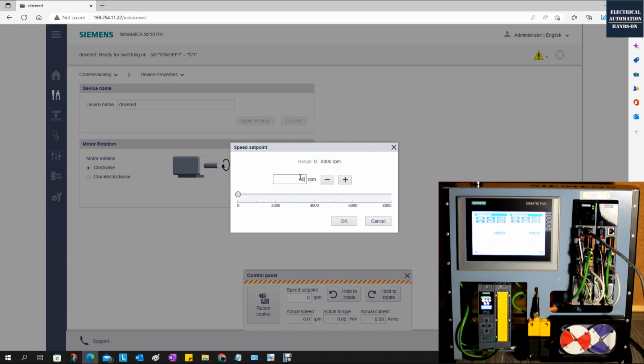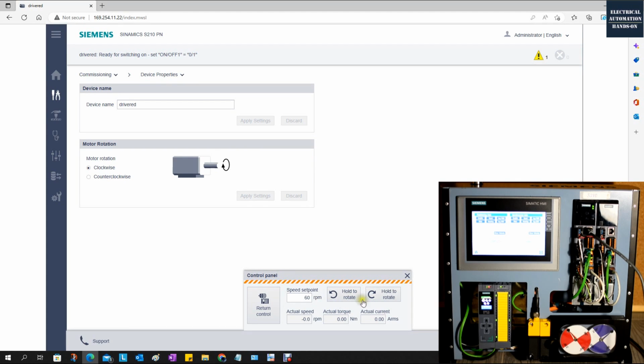I can set 60 RPM. That means in 1 second it will rotate 1 revolution. Okay, click OK. And now I will spin. And in the meantime, we can watch this actual speed, RPM, actual torque, and actual current. Especially this actual torque. At the early beginning, maybe some mechanical parts haven't been connected properly yet. So from this torque value, we can verify if this value makes sense, especially while the motor is empty load. So the torque should be very low. Alright, now let's spin. So let's spin, hold this rotate forward. Turn to the right side.